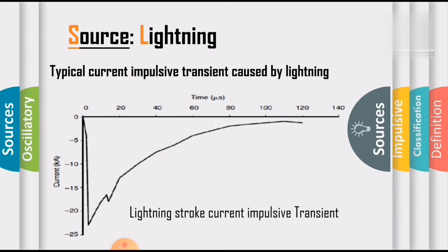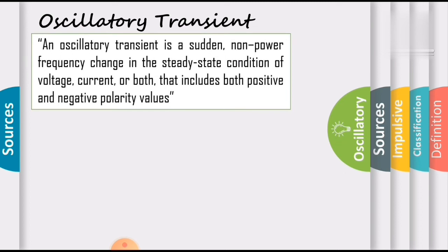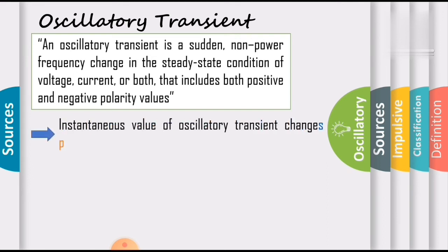From the observation of this waveform, we conclude that an impulsive transient is a sudden non-power frequency change in the steady state condition of voltage, current, or both, that is unidirectional in polarity — and by observing this wave plot, it is confirmed it is only the unidirectional one. The second type is oscillatory transients. An oscillatory transient is a sudden non-power frequency change in the steady state condition of voltage, current, or both, that includes both positive and negative polarity values. The instantaneous values of oscillatory transients change polarity rapidly.